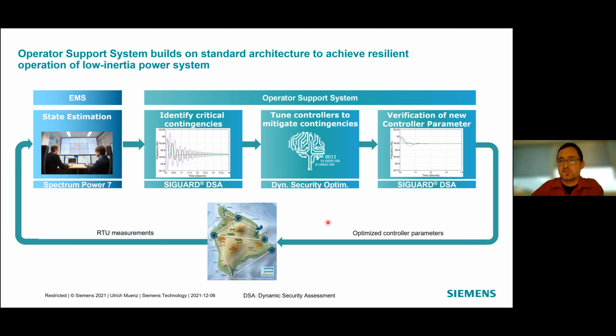It can run slowly. Once we've optimized the controller parameters and sent them to the system, it is N-1 secure and does not require real-time communication or any real-time interaction from the control center. That's very important from our perspective, because utilities usually don't want to rely on adjusting or stabilizing their system during these contingencies in real time.